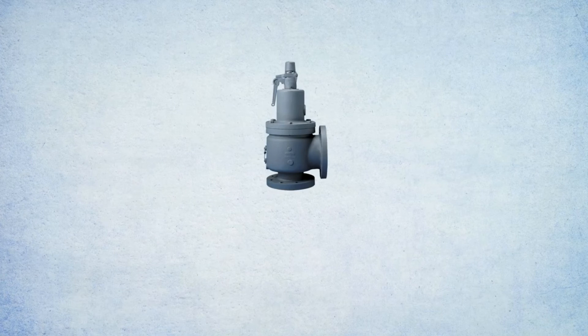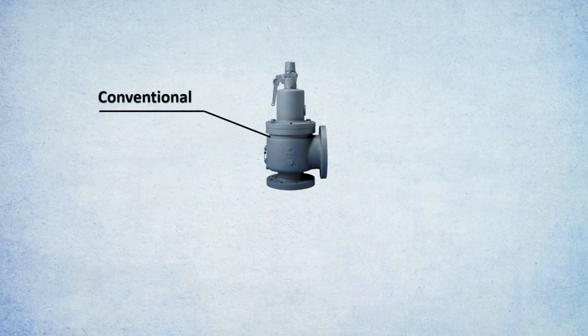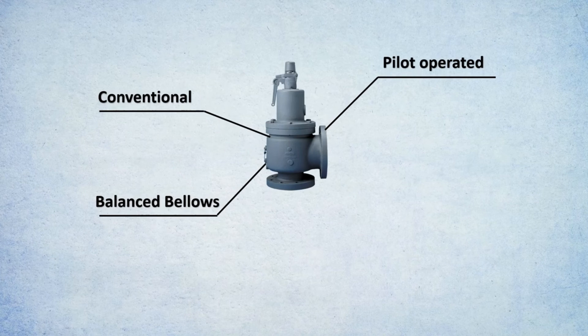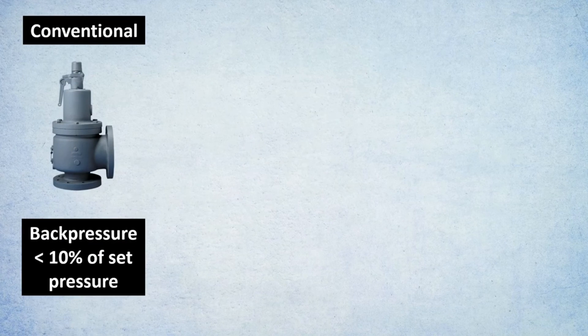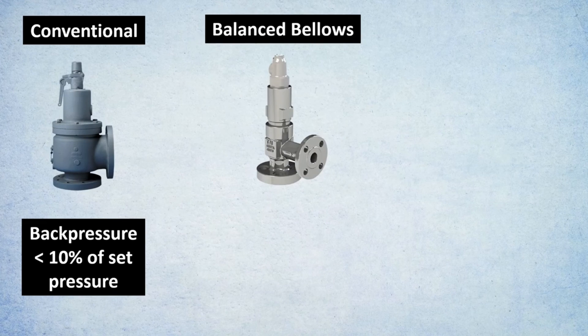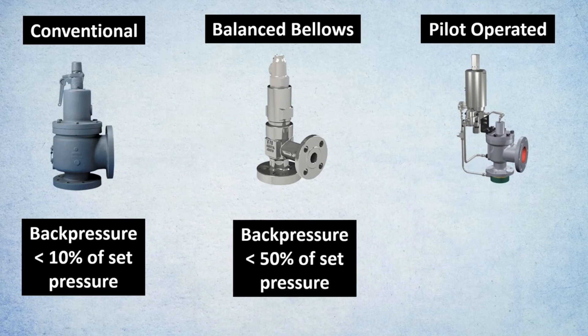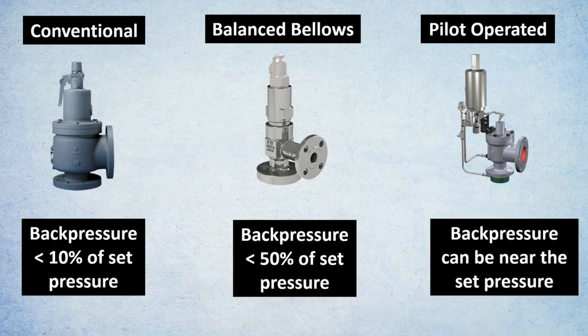To summarize: relief valves are divided into conventional relief valves, balanced bellows relief valves, and pilot operated relief valves. One of the most important selection criteria is the back pressure factor. For conventional relief valves, back pressure must be less than 10 percent of set pressure. For balanced bellows relief valves, it must be less than 50 percent. For pilot operated relief valves, it can be near the set pressure as per vendor recommendation.